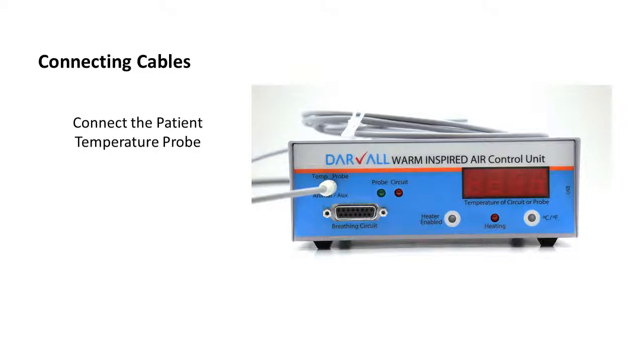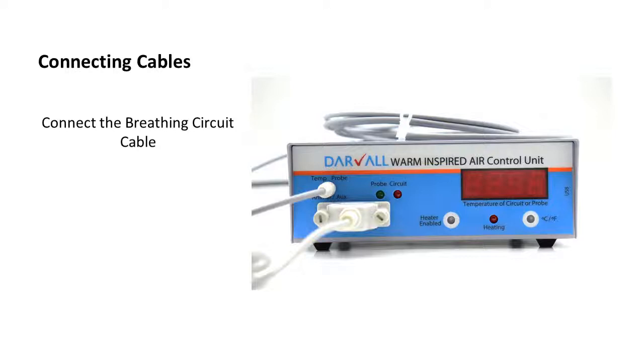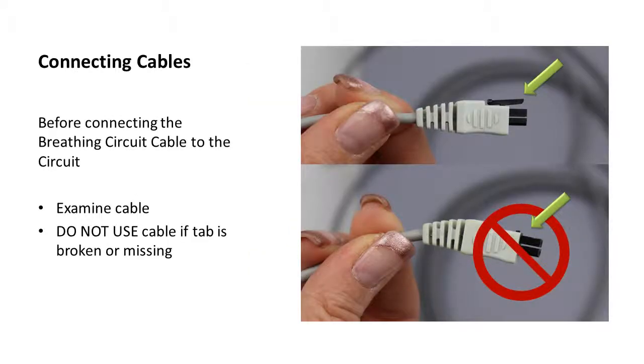Now let's connect the cables and get ready to use the Darvall heated circuit. First, connect the patient temperature probe to the control unit. Connect the breathing circuit cable. Before connecting the breathing circuit cable to the circuit, examine this end of the cable connector. Do not use the cable if the tab on the top of the connector has broken off. That small tab ensures the cable is inserted into the circuit at the proper angle. A cable with a broken tab could be inserted into the circuit at a wrong angle, which may cause damage to the control unit. Damage caused by improper insertion of the cable into the circuit is not covered under warranty.